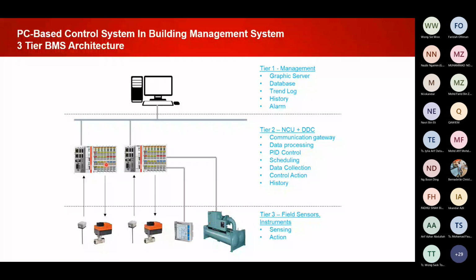So the tier 2 NCU and DDC are already combined into one tier. You can see the system topology becomes simplified, and all the field wiring is direct terminate, and all functions can be integrated directly. So the scheduling feature, PID control, and mobile communication are directly integrated into the controller, and it can also link directly to the workstation SCADA with BACnet communication or other commonly used protocols in the BMS.